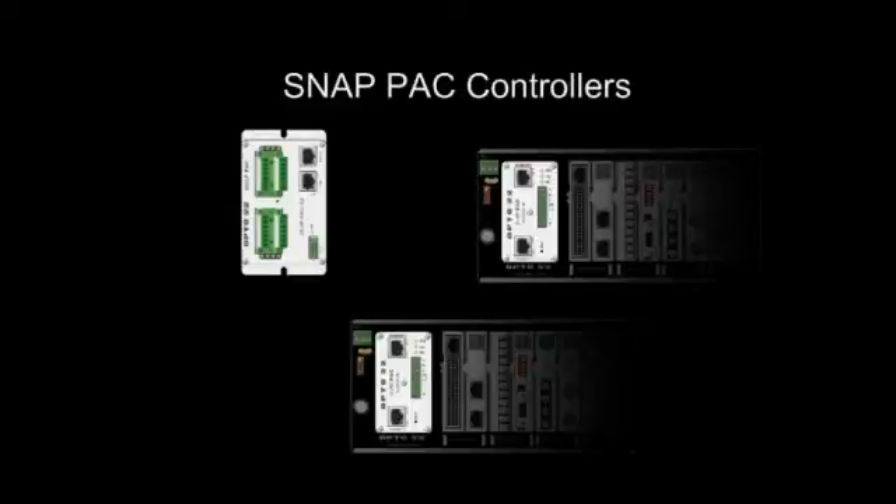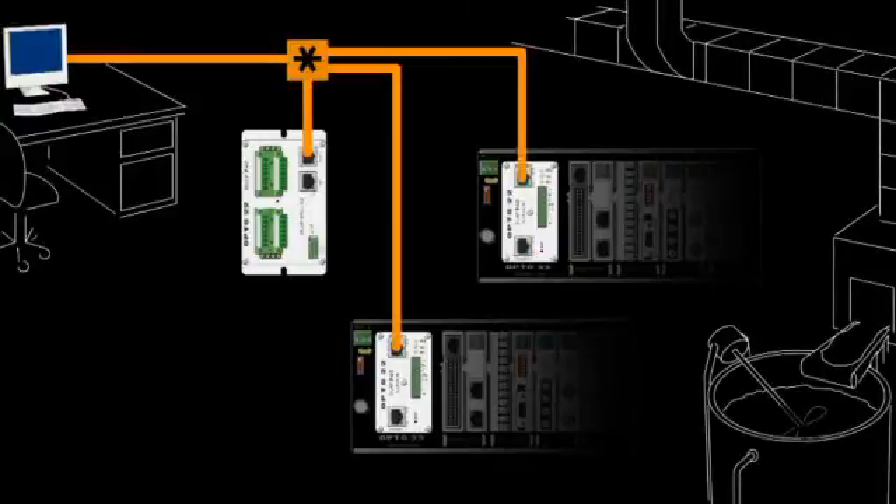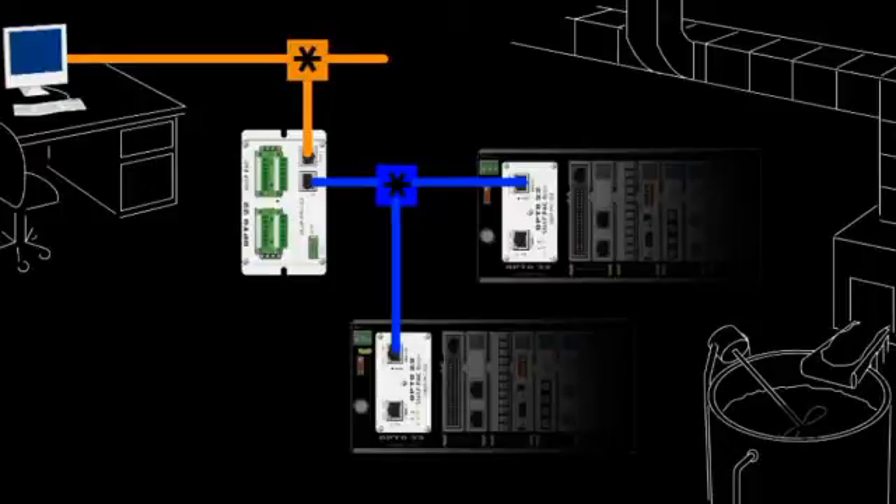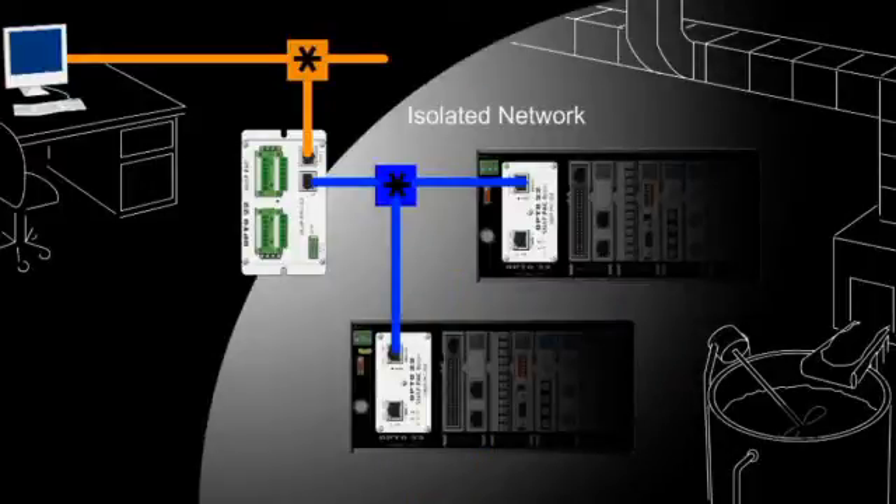On SNAP PAC controllers, these two interfaces are designed to be on separate networks, so each has a unique IP address. They can be configured as redundant network links in the event of a switch or cable failure, or used to segment your I.O. onto a separate network. This isolates your I.O. system from other network traffic.